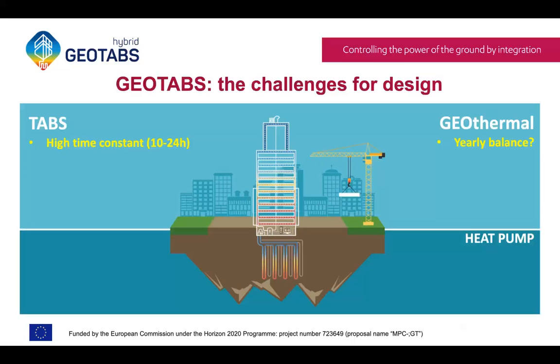To achieve that, there are some additional difficulties that we need to address, namely that a GEOTABS system is not as straightforward to design for as more conventional systems, exactly because of the same properties that also produce its benefits, namely the very high time constants of the emission system, which are typically more than a day long, and of course the constraints of the geothermal heat exchanger that we want to preserve in terms of temperature over a very long time period.